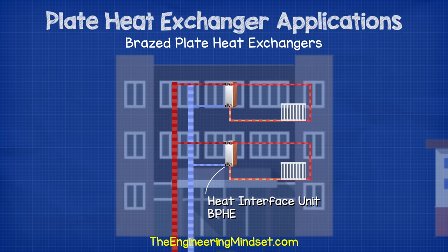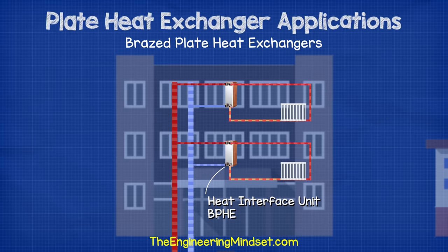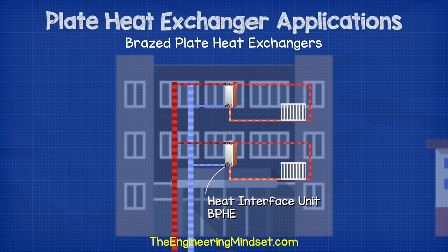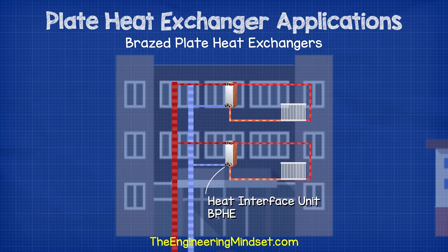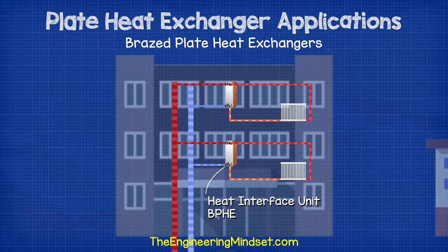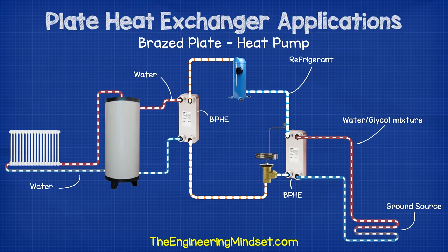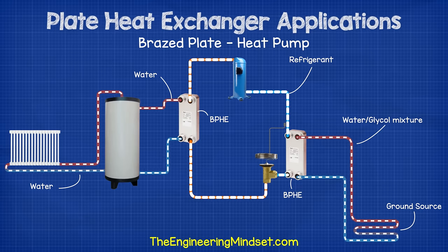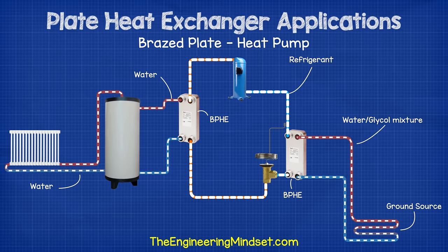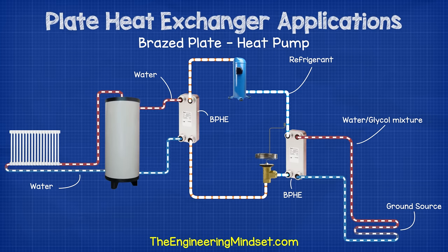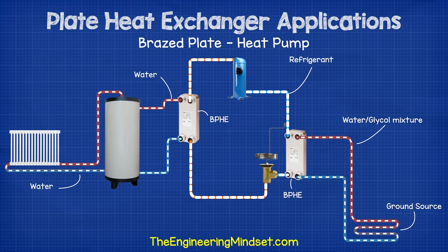For district heating and cooling, heat interface units connecting individual apartments or homes to heating and cooling networks will usually use a brazed plate type heat exchanger. Sometimes larger brazed plate heat exchangers connect buildings to the district network, though the majority are still gasket type. Heat pumps often use brazed plate type heat exchangers to connect separated loops — this is common in water source heat pumps, with brazed plates used for both the condenser and evaporator, separating circuits of water, refrigerant, and water-glycol mixtures.